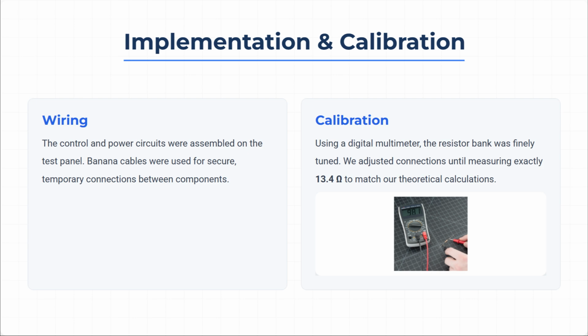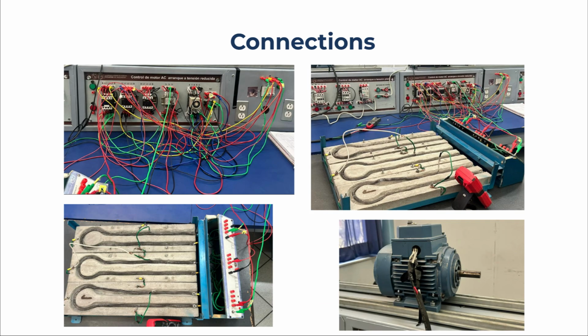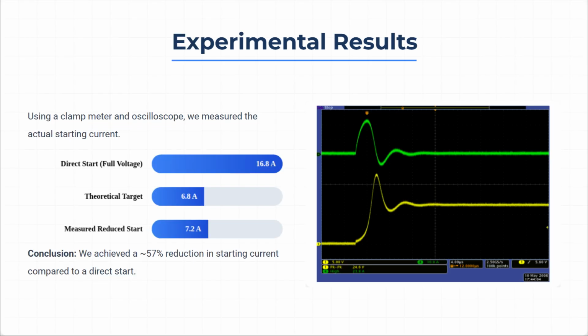Implementation and calibration. The control and power circuits were assembled on the test panel. Calibration was crucial. Using a digital multimeter, we adjusted the resistor bank connection until we measured exactly 13.4 ohms, matching the theoretical requirement. Experimental results. Using a clamp ammeter and oscilloscope, we measured the actual starting current. The estimated direct online start current was 16.8 amperes. Our theoretical target was 6.8 amperes. The measured reduced voltage start value was 7.2 amperes. We achieved approximately 57% reduction in starting current compared to direct start.